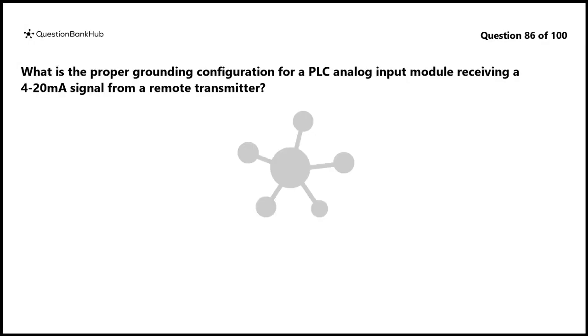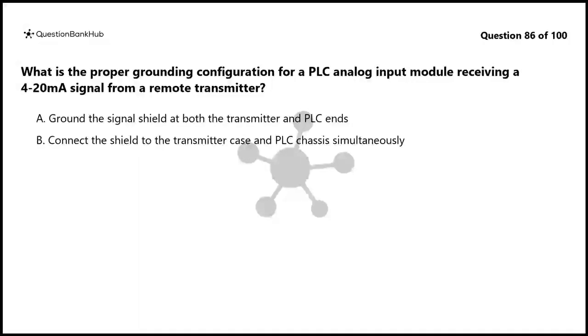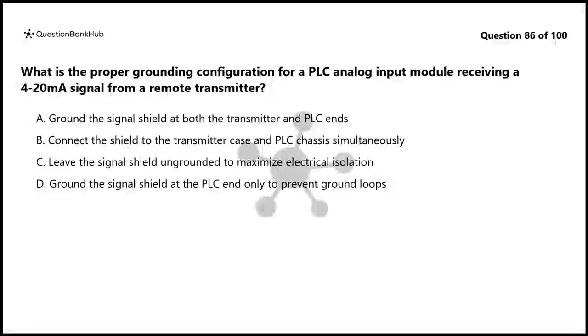Question 86. What is the proper grounding configuration for a PLC analog input module receiving a 4 to 20 mA signal from a remote transmitter? A. Ground the signal shield at both the transmitter and PLC ends. B. Connect the shield to the transmitter case and PLC chassis simultaneously. C. Leave the signal shield ungrounded to maximize electrical isolation. D. Ground the signal shield at the PLC end only to prevent ground loops.